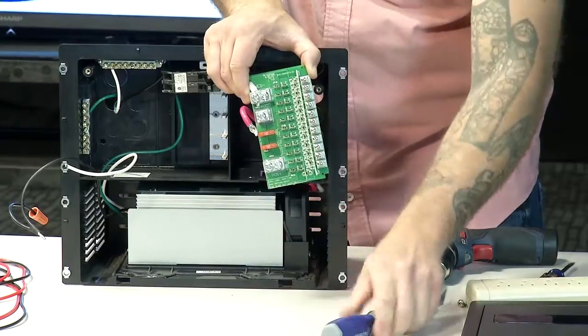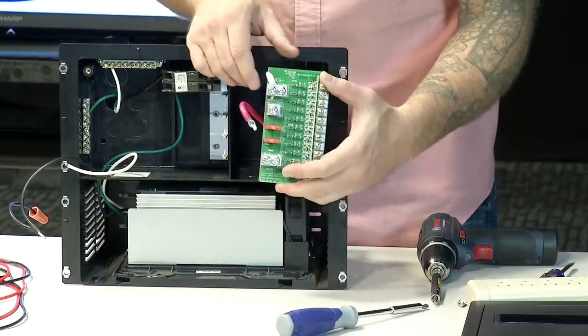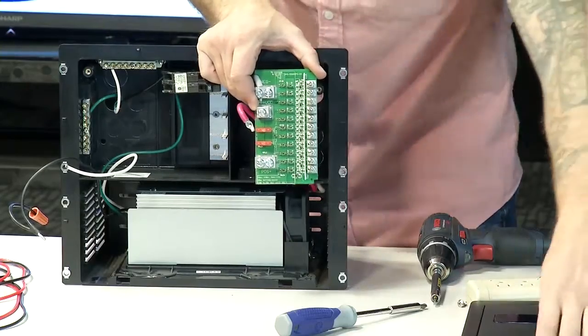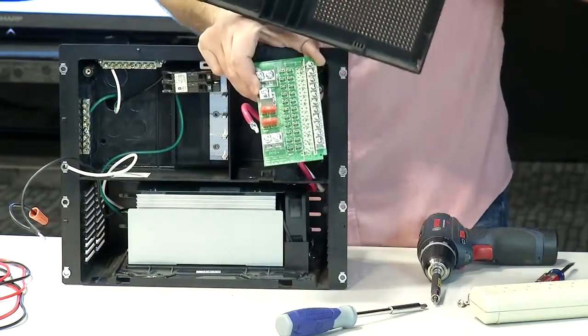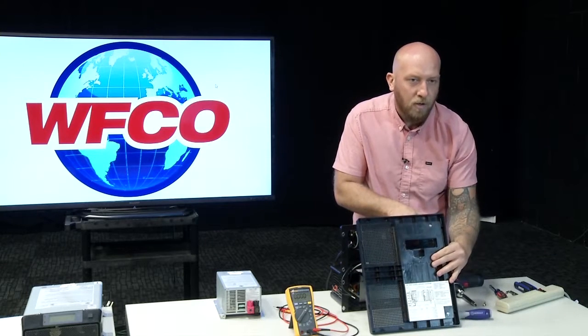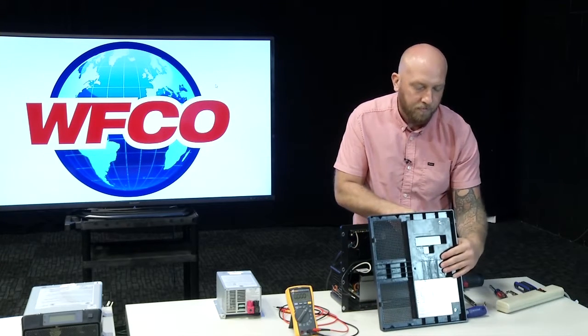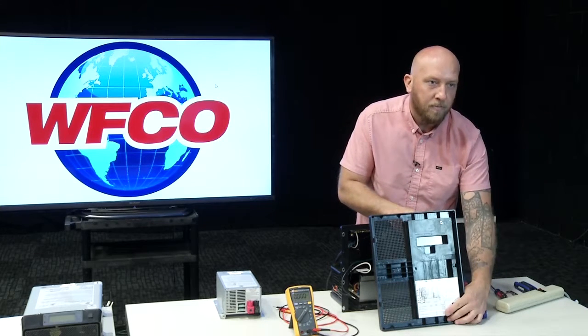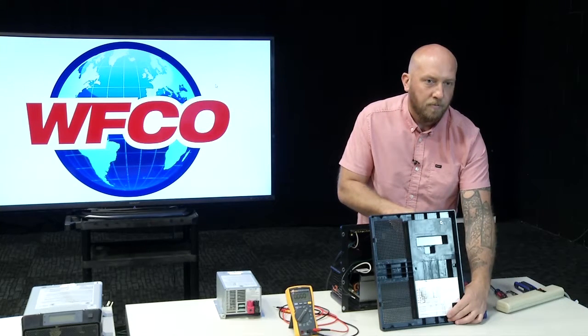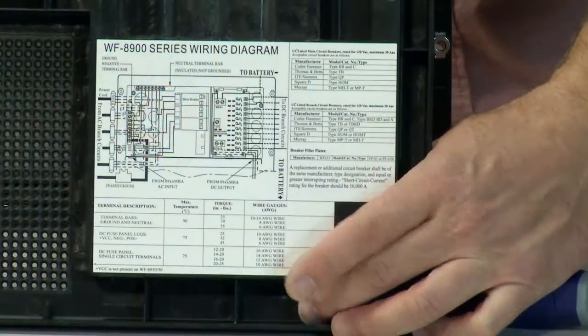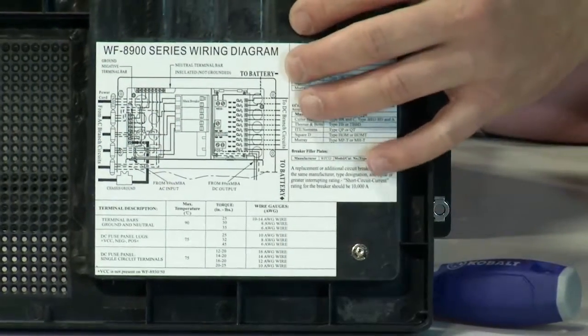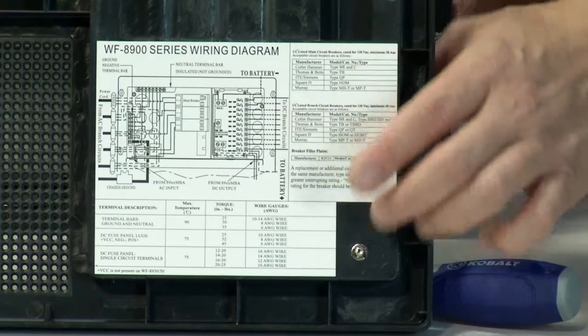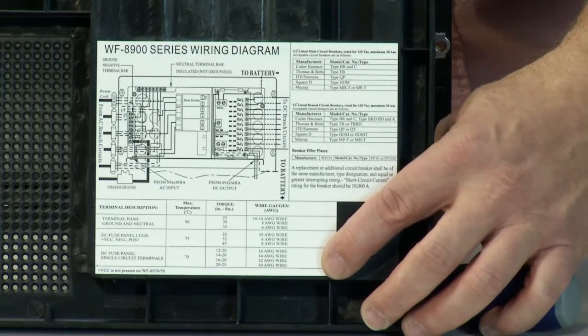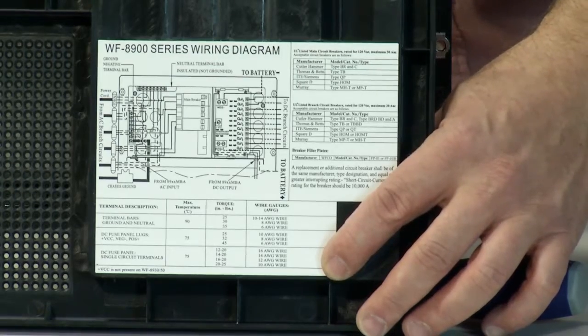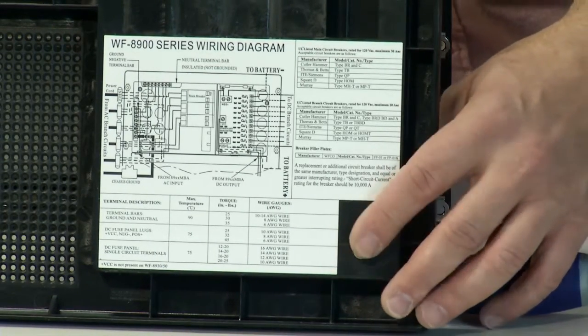There is a torque spec for proper torque on all of the connections on our panels. If you look at the back of our door assembly that we took off to get to the main board, right down here at the bottom, we've got all of our torque specs and a wiring diagram. All of our power centers have a wiring diagram and torque specs for your AC and DC connections, so when you're putting in a new main board or rewiring your AC side, there are torque specs to go by.